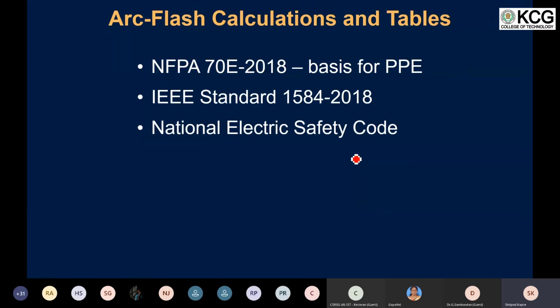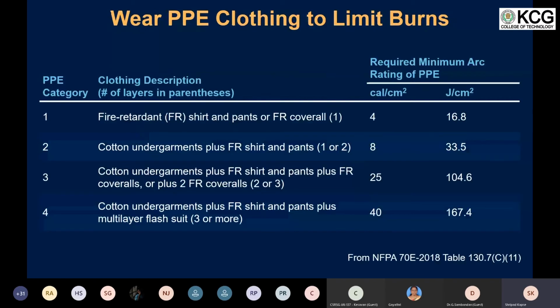So from the NFPA 70E, the faults are categorized into four scenarios: category 1, category 2, category 3, and category 4 faults. And there is associated PPE. Category 1 can withstand up to 4 calories per centimeter square. Category 2 can withstand up to 8 calories, and category 3 and 4 can withstand up to 25 and 40 calories per centimeter square.